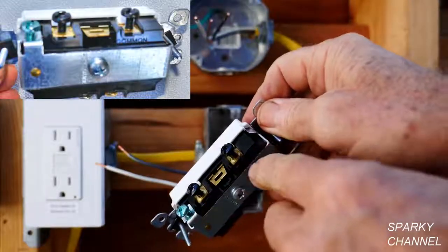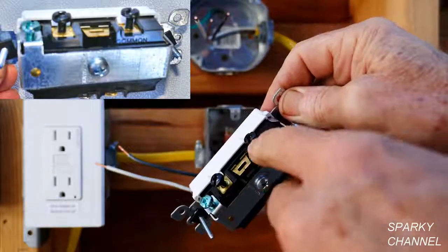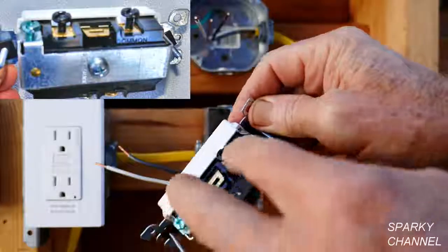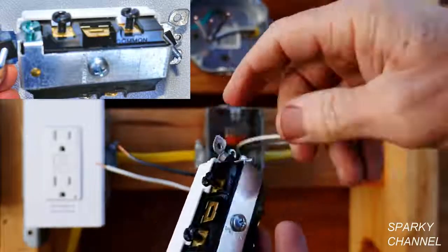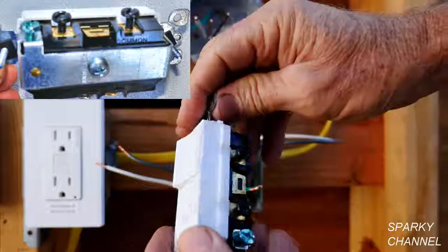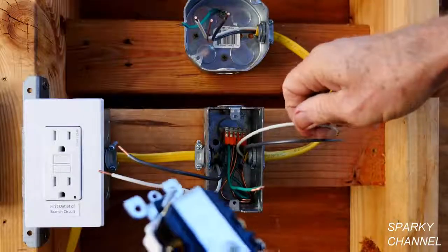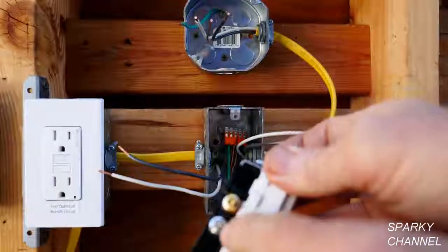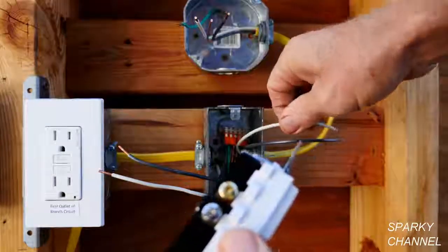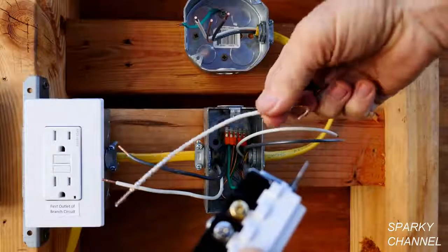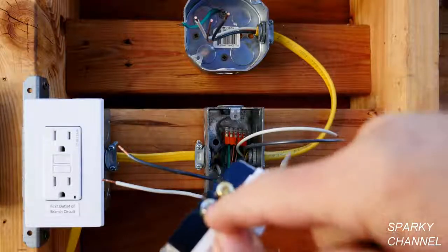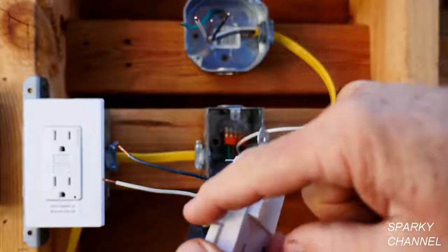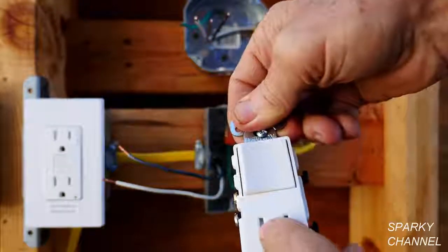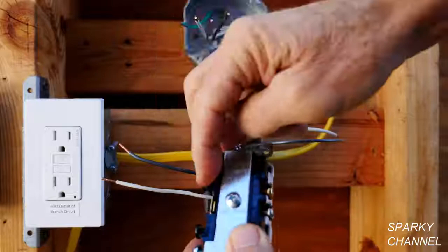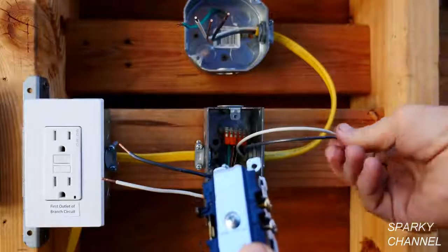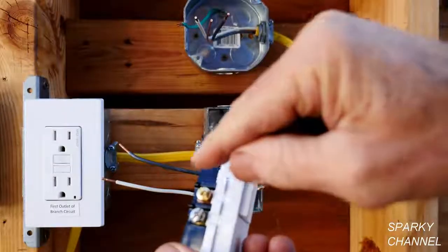You see, if I connect it here to the common, there's a connector right here that connects these 2 terminals together. So if I put the hot wire here, both of the sides are hot. Okay, so I only need to put 1 hot wire to get both of these devices hot. Now, I have 2 neutrals, and I have 1 silver terminal on the other side and 1 bronze terminal. So I'm going to be connecting these 2 neutrals together with a Wago lever nut and using a pigtail to serve this silver terminal. And that neutral wire, which will be connected to the silver terminal, will provide a neutral for the receptacle.